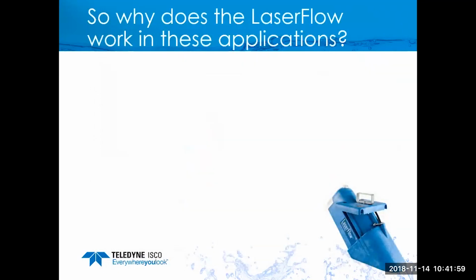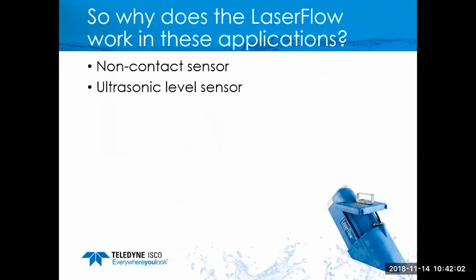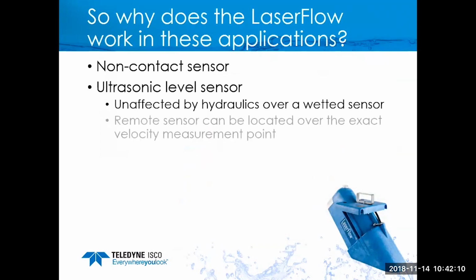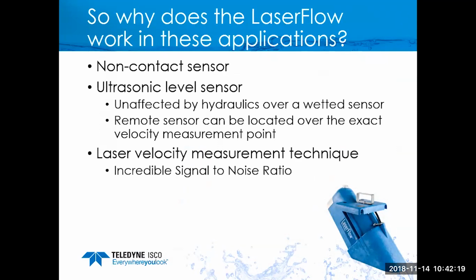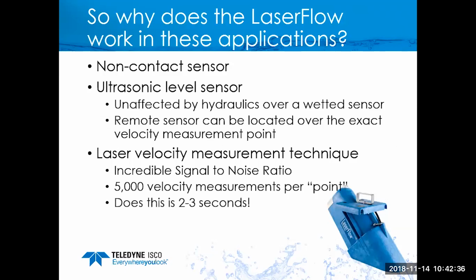Okay, so why does the laser work in these applications? Well, it's non-contact, so it's not going to get covered. It uses an ultrasonic sensor that doesn't drift and is not affected by wetted hydraulics over wetted sensors like we showed you. Remote ultrasonic is key because now we can put it at the exact same point that we're measuring velocity to improve accuracy. The laser measurement technique is pretty incredible. The signal to noise ratio is phenomenal, and that helps us, again, really pick into very difficult applications. We take 5,000 velocity measurements per point. Again, we do that in a very short amount of time, 2 to 3 seconds.